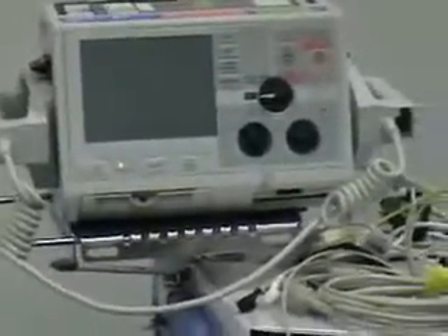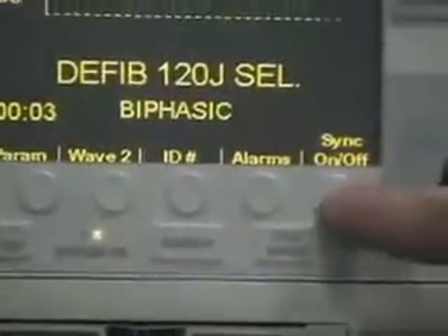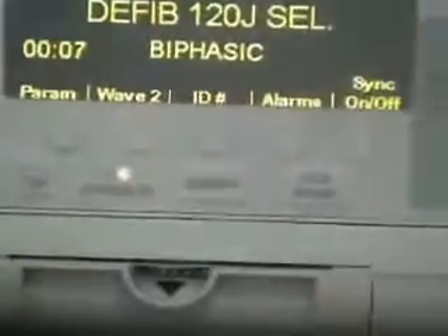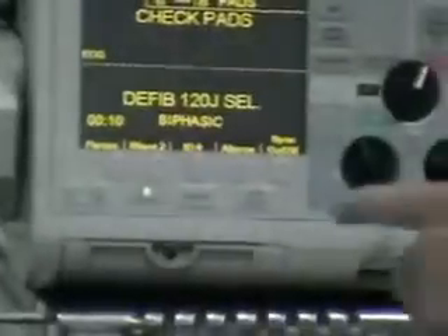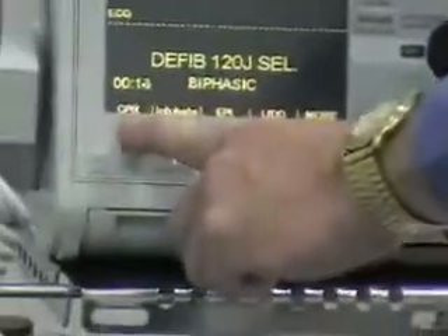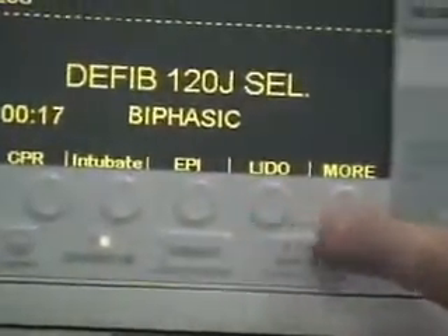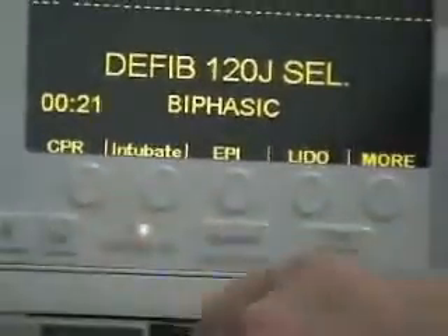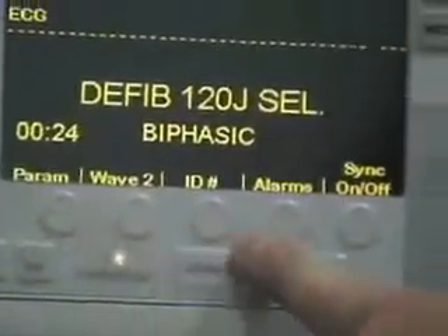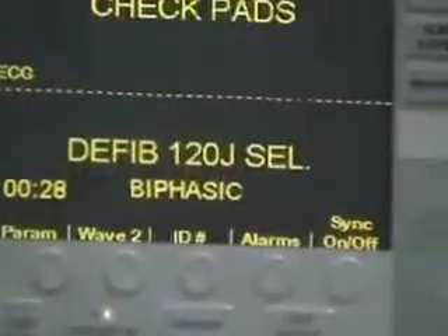What's really nice about these new Zolls too is that you can type in right away the patient's name, and as you're giving the medication, it marks that all for you. This one actually does that. If you're in a code situation, this has what's called a code marker, and there are additional buttons that will show up. Check pad. You have alarms, you have multiple parameters that can be identified. And on the code marker, if you push that hard button, you'll see here it says CPR, intubate, epinephrine, lidocaine, and there's even a list of other things, so that you can then take the soft button underneath and press the appropriate button, and that information will be printed out on the scroll of paper as it comes out.